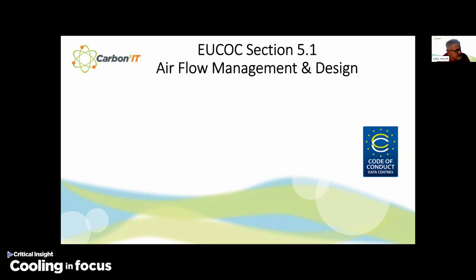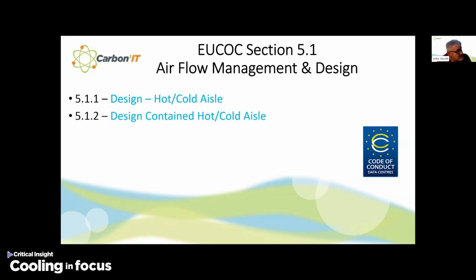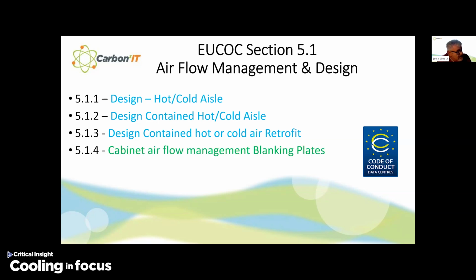So let's look at the first section, airflow management and design. First best practice for new builds and retrofit is design for the hot and cold aisle. Second is design for contained hot and cold aisle. Third is design and contain for hot and cold air retrofit. Then manage that air using cabinet airflow management blanking plates.